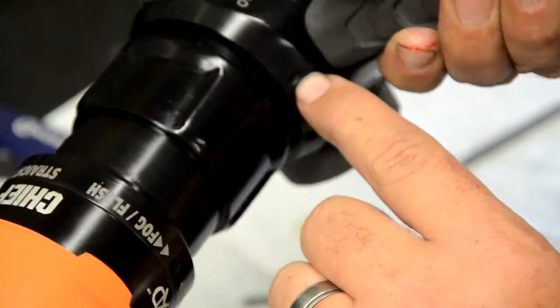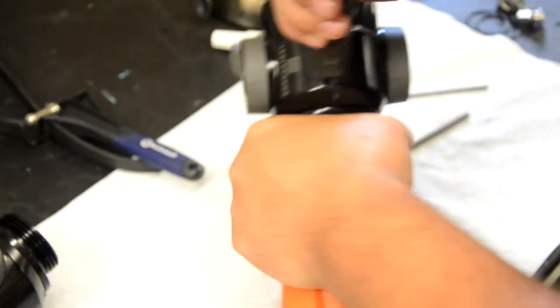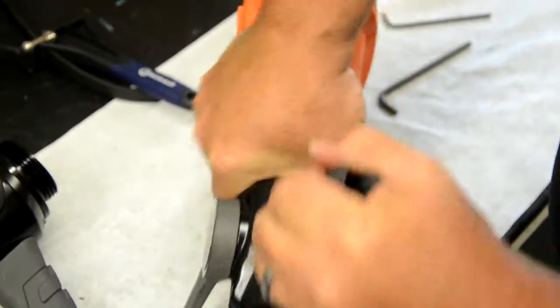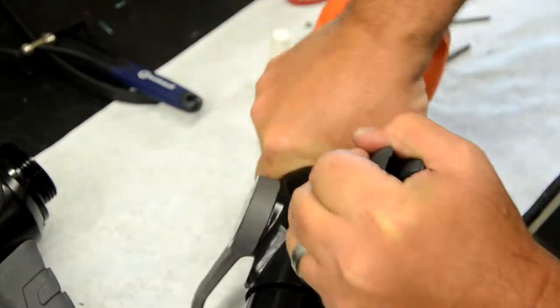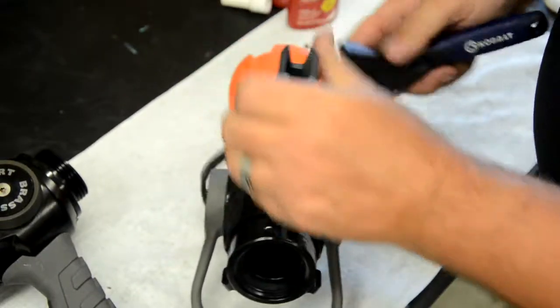Using the strap wrench, thread and tighten the nozzle tip onto the shutoff body. Watch for the pre-drilled hole from the factory assembly and line that up with the set screw hole in the bottom of the shutoff body. We recommend placing a small piece of tape or something to temporarily mark that area on the nozzle tip to help you align it a lot easier.